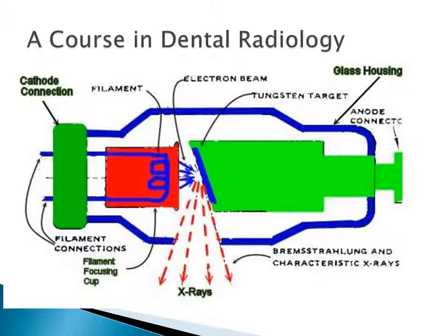This is a diagram of an actual X-ray tube head. So what's going on is this is my filament. So this is the part that I'm going to get super, super hot. When I heat it up, or when I apply my mA, my milliamps, through this stream right here, what's going to happen is that is going to generate lots and lots of heat, which will then allow my electrons to pool up right here.